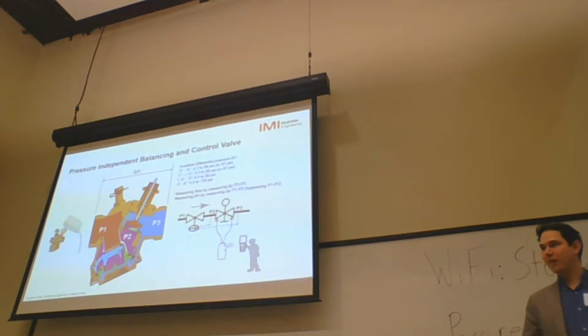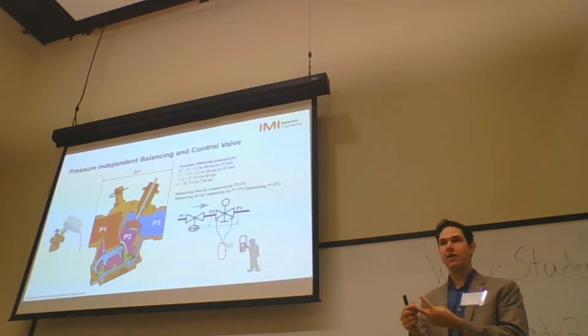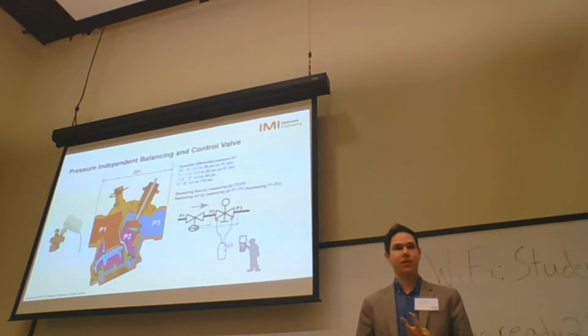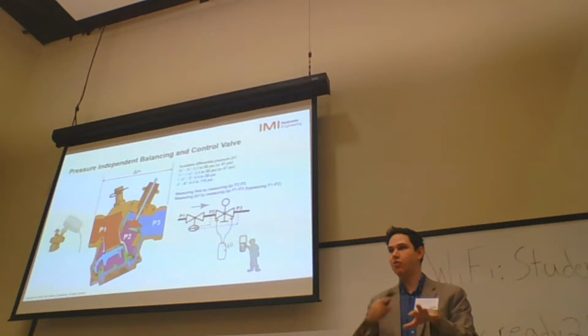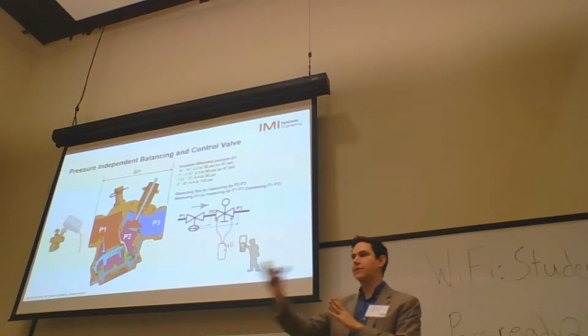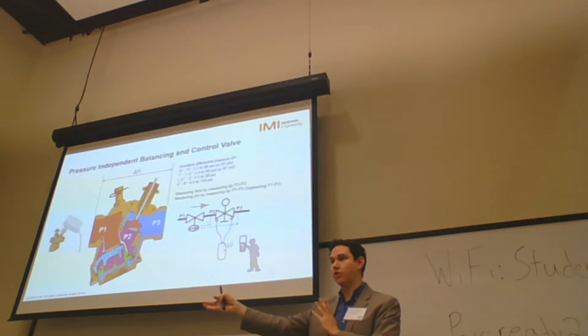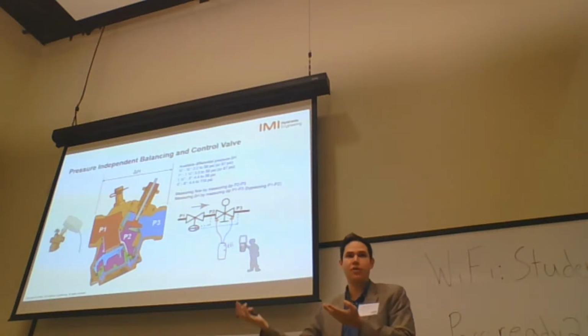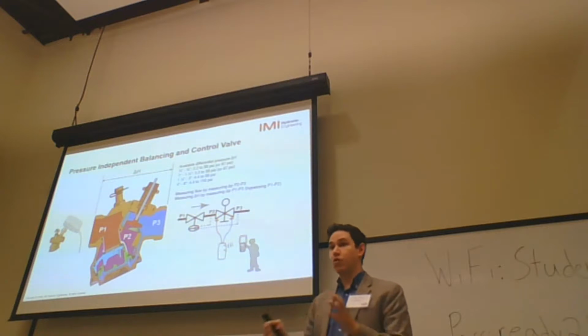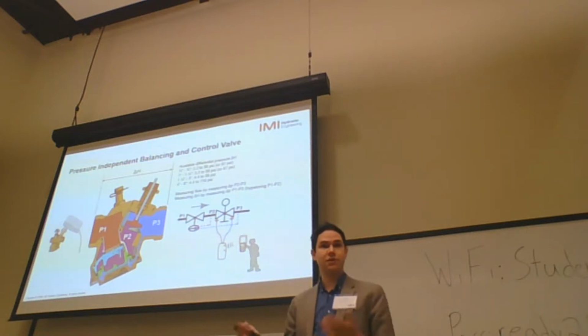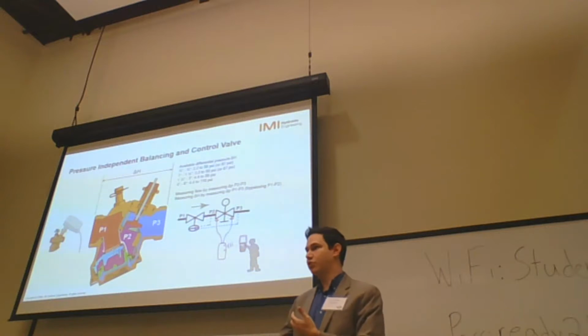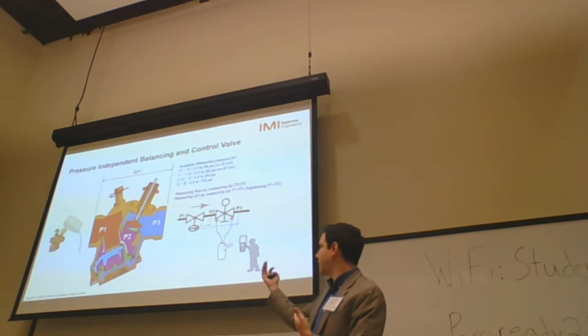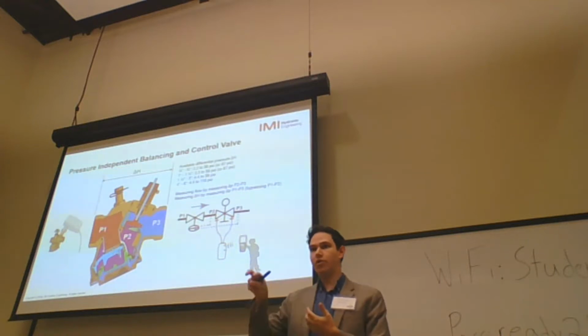What is the advantage of measuring the available pressure? I would say two, basically, for troubleshooting an installation. First, when you try to identify what is your index circuit on your system. So basically the designer calculated the pump head thinking about one index path until your index coil for the whole installation. Could be the last one or not always, but it's one index coil. Contractors are always changing pipes, and pressure drops in the system may not be the same after construction. So the advantage of measuring the available pressure is finding the lowest available pressure that you have on your coils.